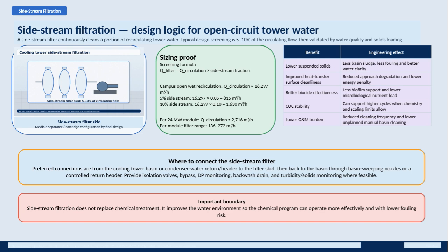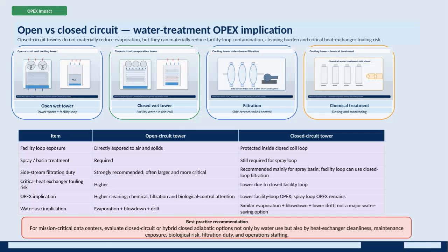This combination of mechanical and chemical treatment ensures long-term operational efficiency and reliability. Let's examine the operational expenditure, or OPEX, impact when choosing between open and closed-circuit cooling towers and water treatment systems. Closed-circuit towers don't significantly reduce evaporation compared to open circuits, so water savings aren't substantial. However, they do offer important benefits by reducing contamination in the facility loop, lowering the cleaning requirements, and decreasing the risk of fouling in critical heat exchangers.